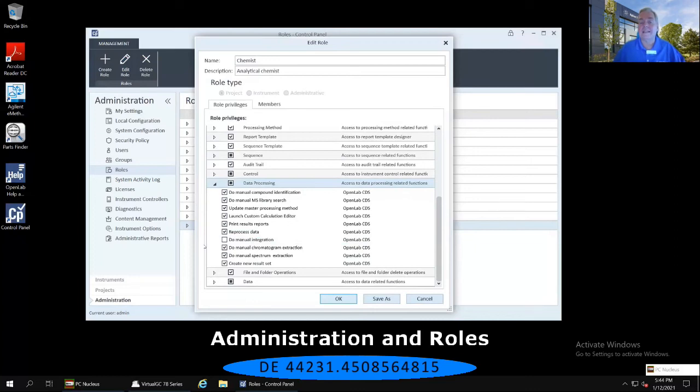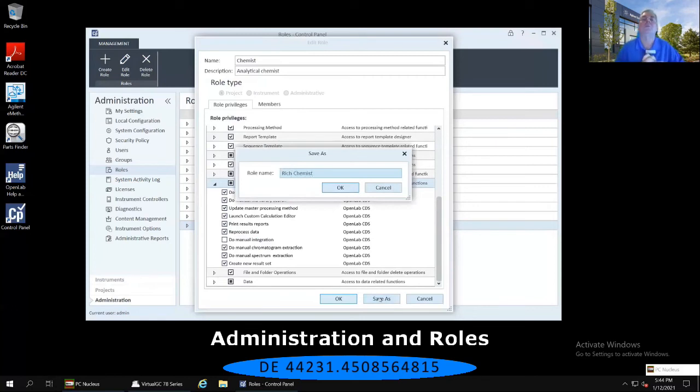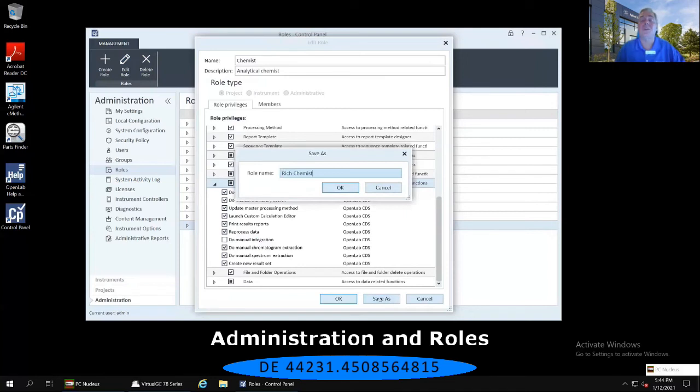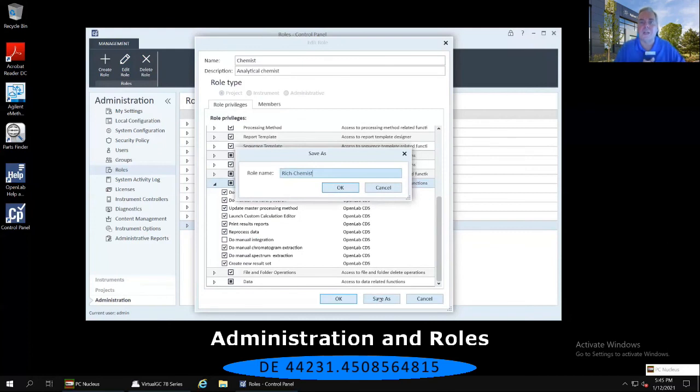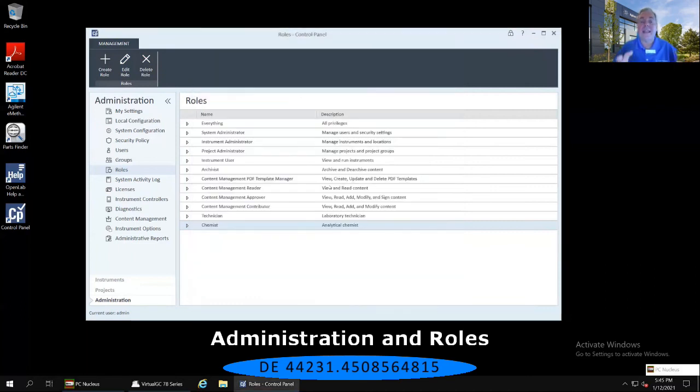So I'm going to select the save as icon at the bottom of this edit role window, and I am going to type in the name of my new role. I'm going to call it a rich-chemist role. You can call it whatever role you wish, but the reason I suggest you don't overwrite the roles that Agilent gives you out of the box is because there's no easy way for you to get back those default roles if you overwrite them. The only way to do that is to really go back to the role and undo any of the changes you've made and save it back to the chemist role. So instead, I suggest that you save as and click OK, and that now creates a brand new role for us in our list of roles that are available here.